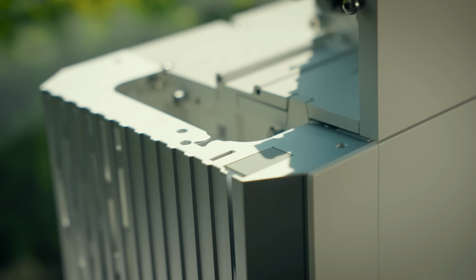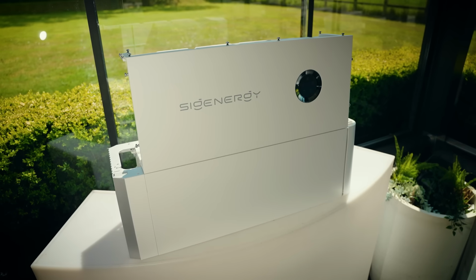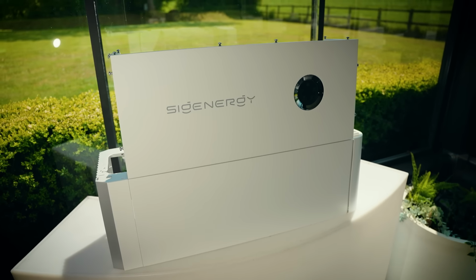With the different energy controller sizes, they actually upgrade a few of the other parts as well. What normally happens with inverter sizes is you get either 2 or 3 maximum power point trackers. Sometimes you don't need them and you're buying them for no reason, and other times you don't have enough, so you end up using optimizers instead, which often need those parts alongside.